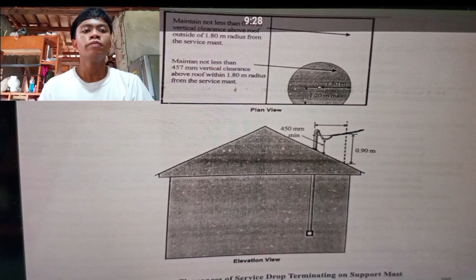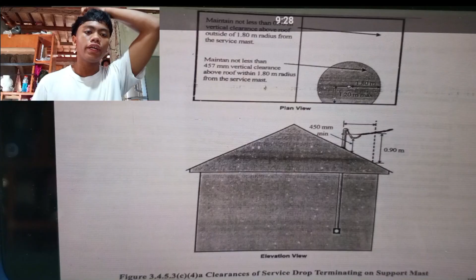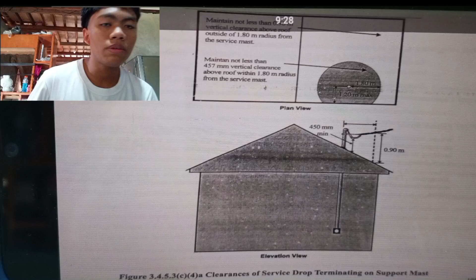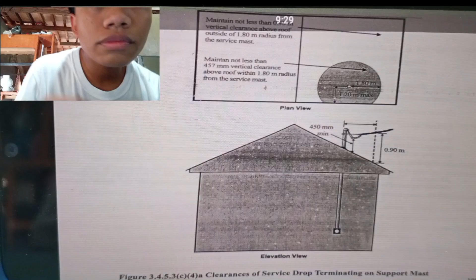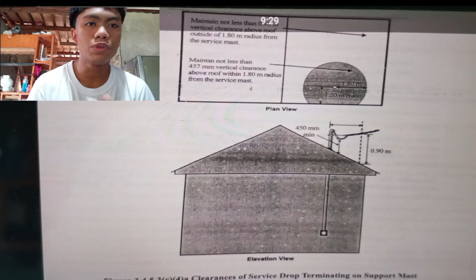So this is Figure 3.4.5.3, clearances of a service drop terminating on a support mast. As you can see, maintain not less than 0.90. This is also a diagram for this topic. So maintain not less than 0.90 meter vertical clearance above the roof outside of a 1.80 meter radius from the service mast.